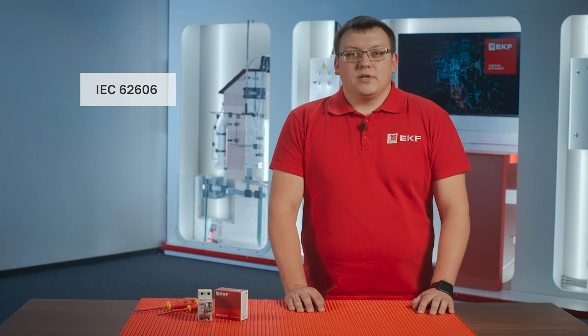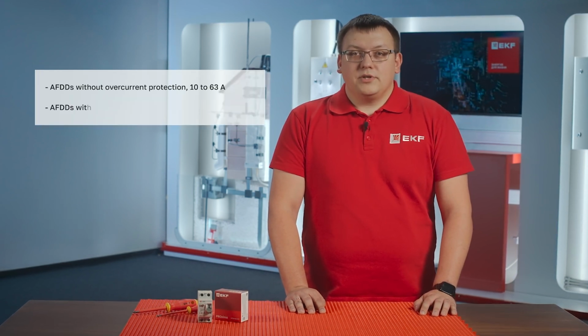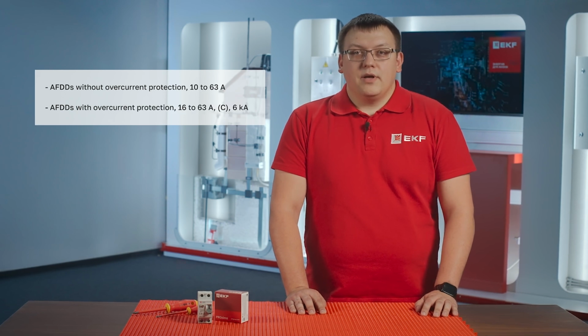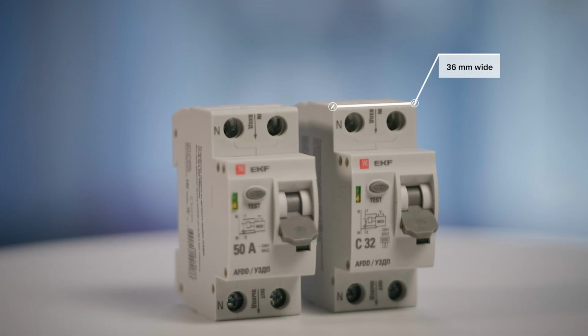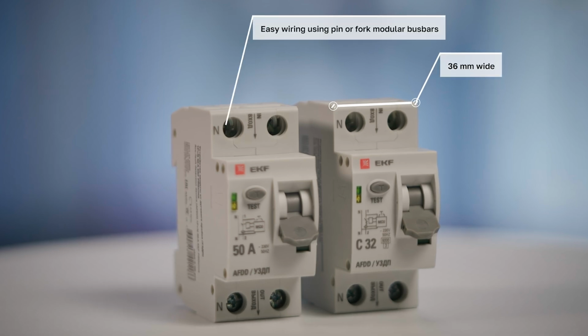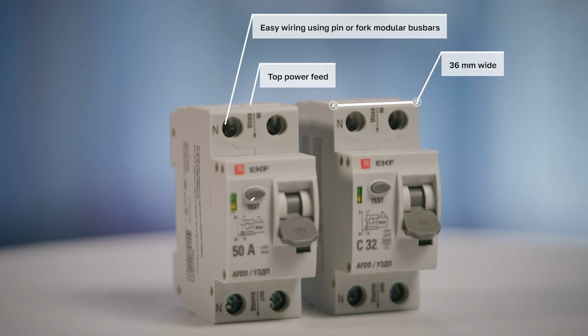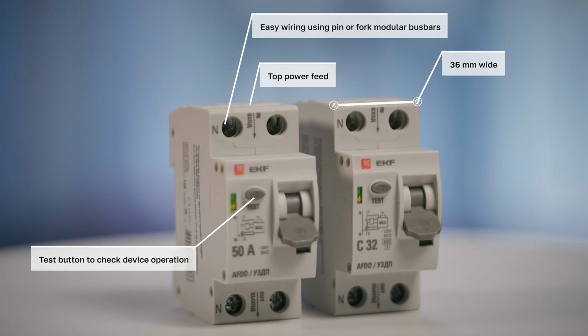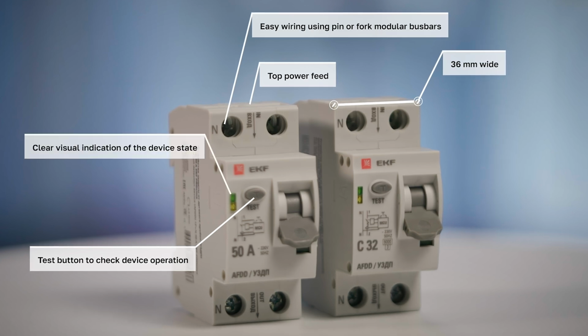EKF product range includes two versions of single-phase AFDDs. AFDDs without an integrated circuit breaker, rated for 10 to 63 amps. AFDDs with an integrated circuit breaker, rated for 16 to 63 amps with a C-curve, 6 kiloamps. Design features. This device is 36 mm or 2 modules wide, with easy wiring using pin or fork modular bus bars, both from the top and from the bottom. Top power feed. Test button to check whether the device is operating properly. Clear visual indication of the device state.